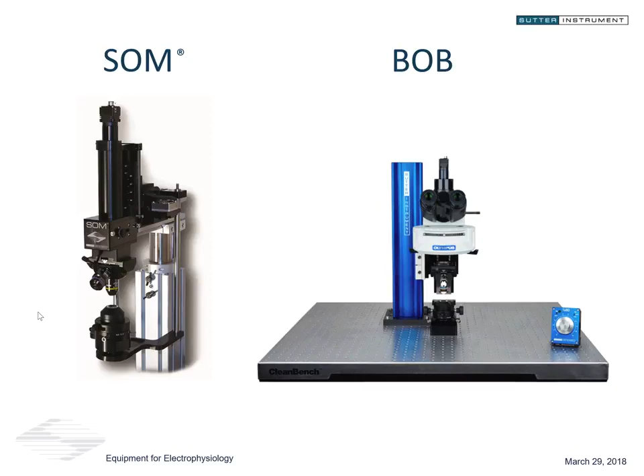Well, here's a question that I'll probably take on myself. They want to know if the IPA or the D-patch amplifier can control the timing or intensity of the light sources, including the Lambda 421. The answer is yes. Both the IPA and the D-patch do have auxiliary outputs as well as TTL outputs that can be controlled by the SutterPatch software, not just by setting a value, but we could actually create all sorts of custom waveforms to drive the device to actually regulate all of the timing. So yeah, that's quite easy, and not only for light sources, but all sorts of other systems like perfusion systems, for example.